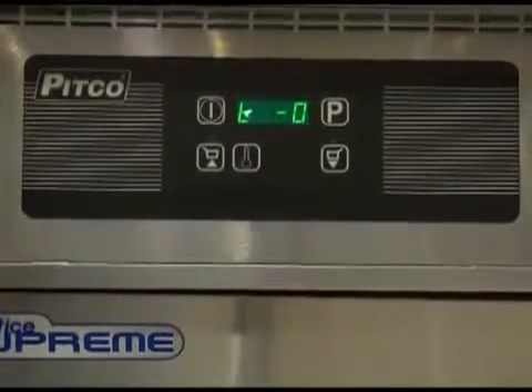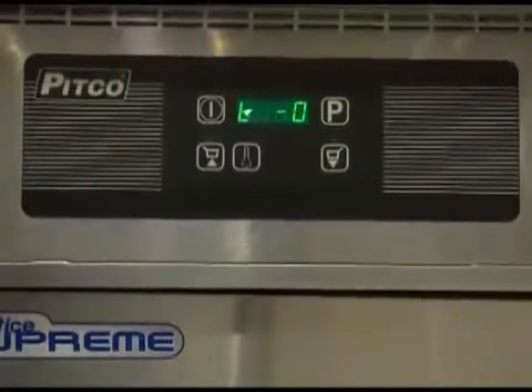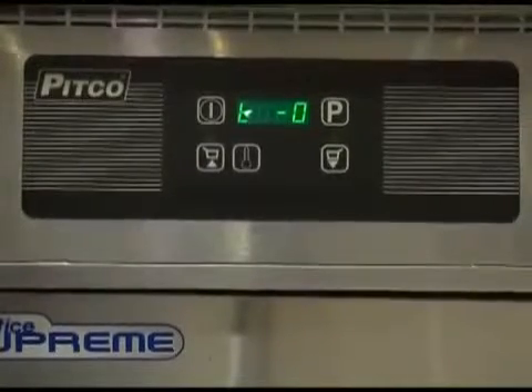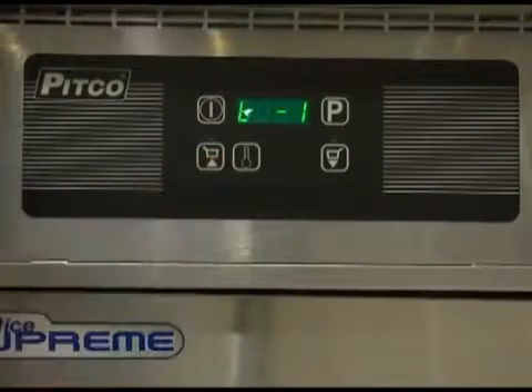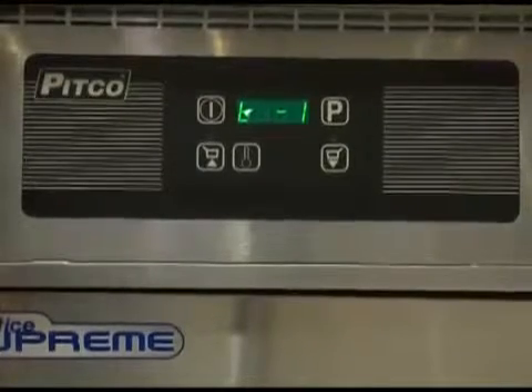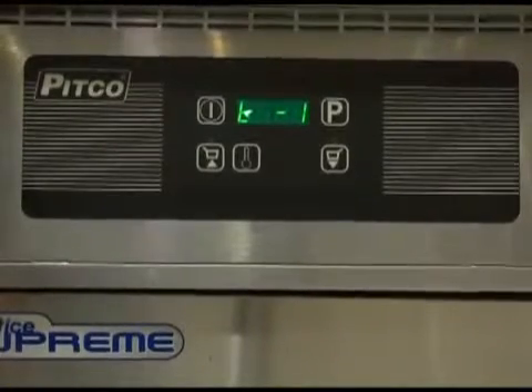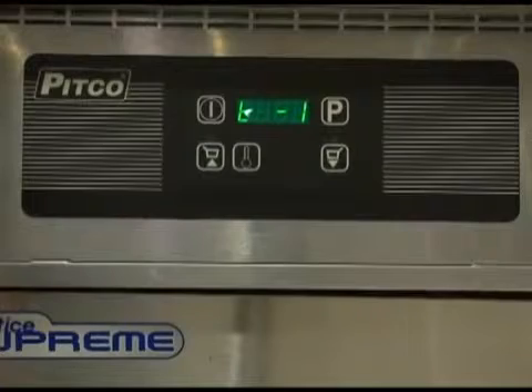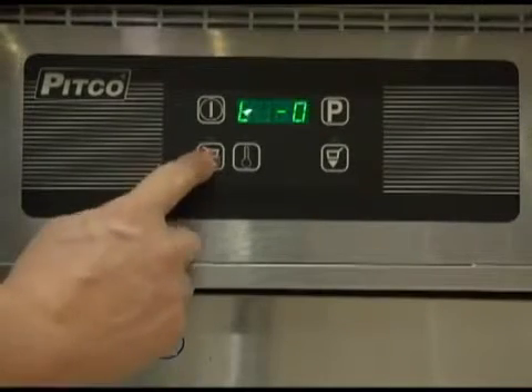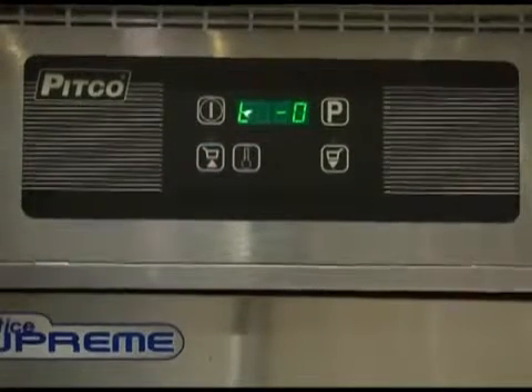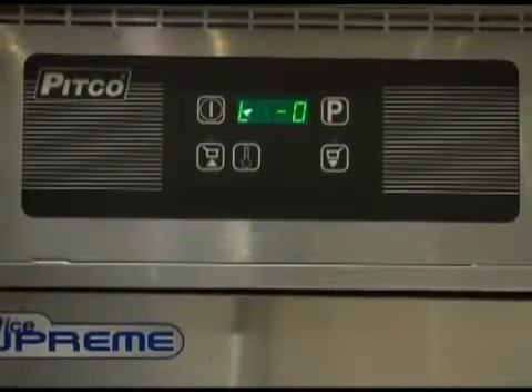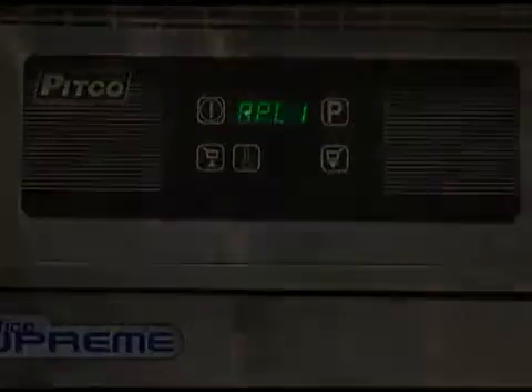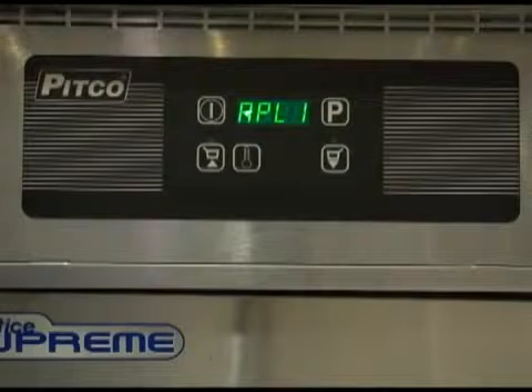Oil temperatures can be displayed rather than normal operating displays. T0 is the normal setting for the displays, and T1 is selected to display oil temperatures. The T1 setting is intended as an aid to troubleshooting the fryer performance only. This setting should always be returned to the T0 setting for normal operation. Once set correctly, press the program key to save and go on to the next option.